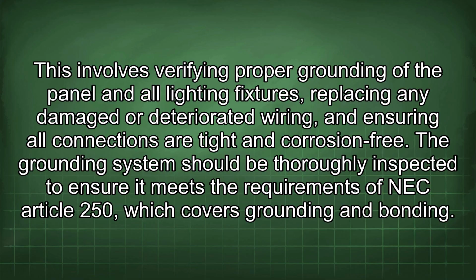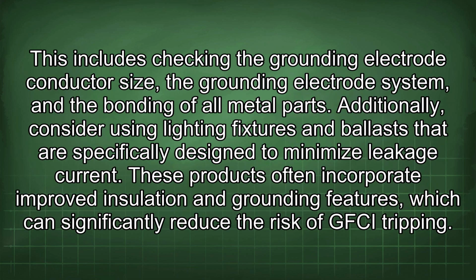The grounding system should be thoroughly inspected to ensure it meets the requirements of NEC Article 250, which covers grounding and bonding. This includes checking the grounding electrode conductor size, the grounding electrode system, and the bonding of all metal parts. Additionally, consider using lighting fixtures and ballasts that are specifically designed to minimize leakage current. These products often incorporate improved insulation and grounding features, which can significantly reduce the risk of GFCI tripping.